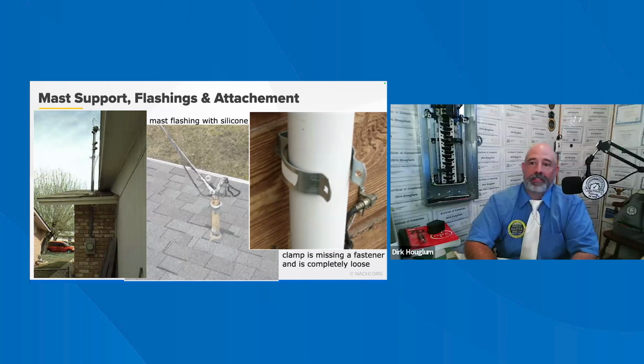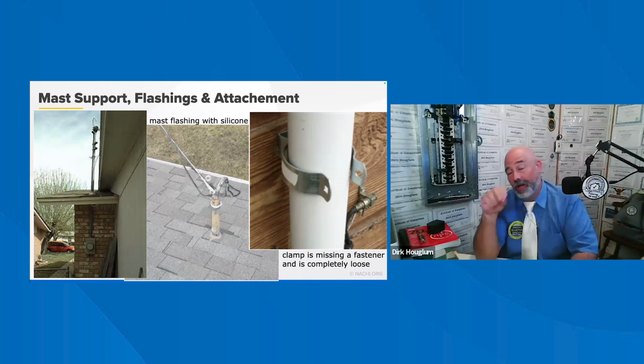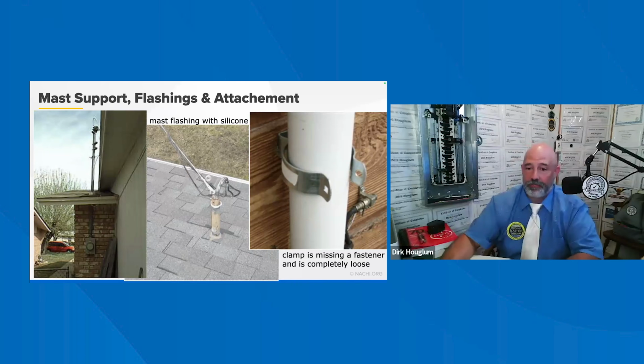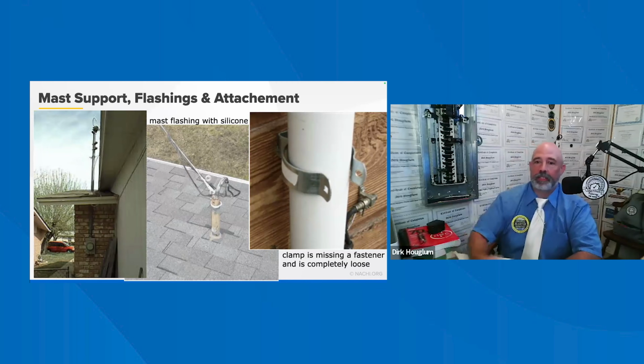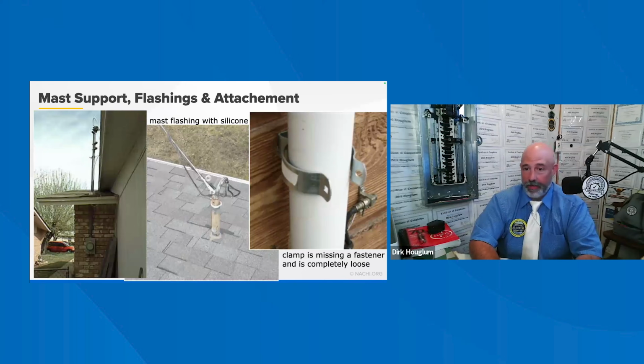The overhead mast must not support such things as cable TV, telephone wires, and so on and so forth. The inspector should report on all these and say further evaluation from a licensed electrician. Now, the IRC is silent on the size requirement of conduit type to be used in the masts or risers. It is also silent about the height above the roof it can extend before supporting any braces or the guy wires. In many jurisdictions, the power utility company specifies that requirement.